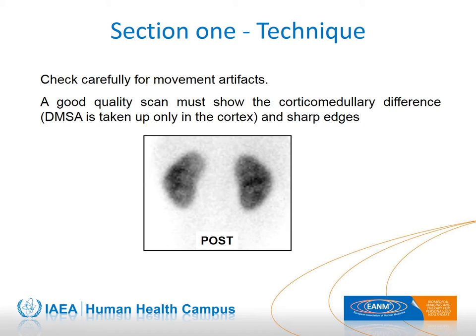Since DMSA is taken up only in the kidney cortex, the kidney's picture must show the cortical-medullary differentiation. A loss of visualization of this relation can be attributed to movement, the use of a wrong collimator, excessive distance between the table and the camera head, or an incorrect energy peak setting.